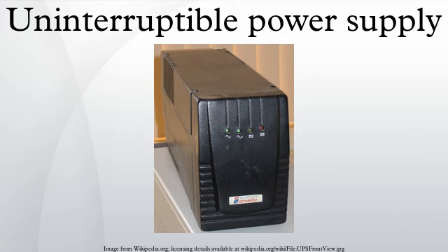Case no. A1 uses an integrated flywheel as a short-term energy source instead of batteries to allow time for external, electrically coupled gensets to start and be brought online. Cases no. A2 and A3 can use batteries or a freestanding electrically coupled flywheel as the short-term energy source.